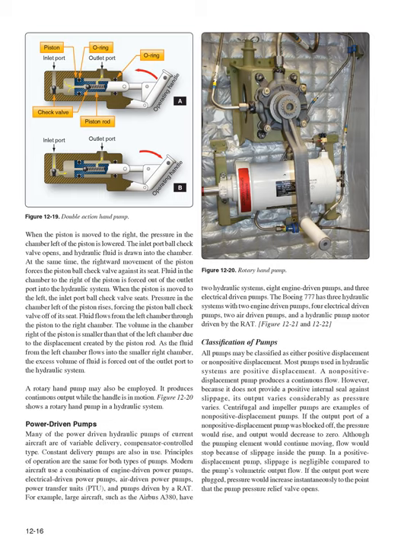If the output port of a non-positive displacement pump was blocked off, the pressure would rise, and output would decrease to zero. Although the pumping element would continue moving, flow would stop because of slippage inside the pump. In a positive displacement pump, slippage is negligible compared to the pump's volumetric output flow. If the output port were plugged, pressure would increase instantaneously to the point that the pump pressure relief valve opens.